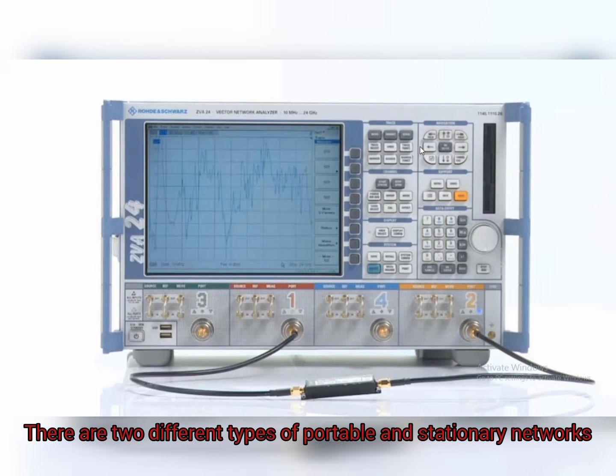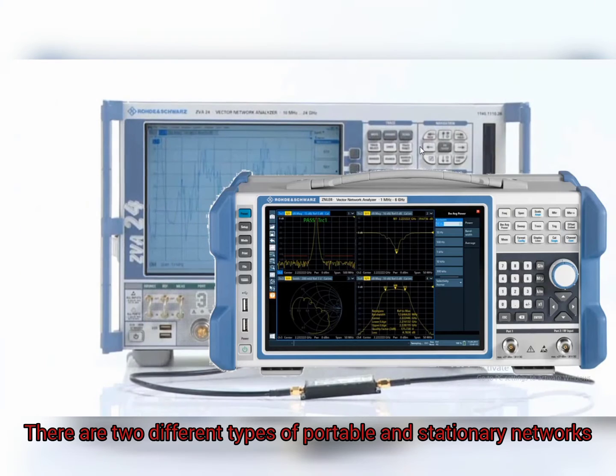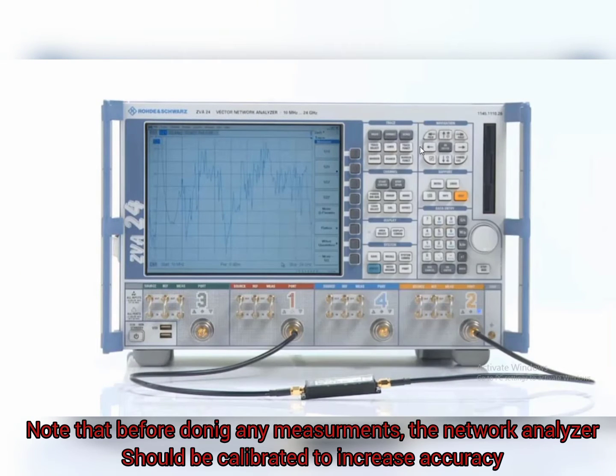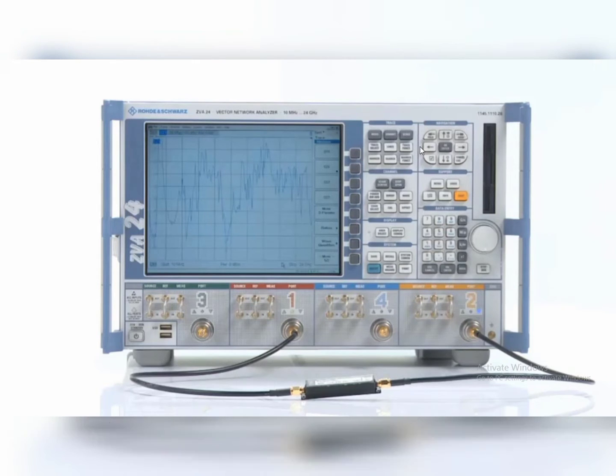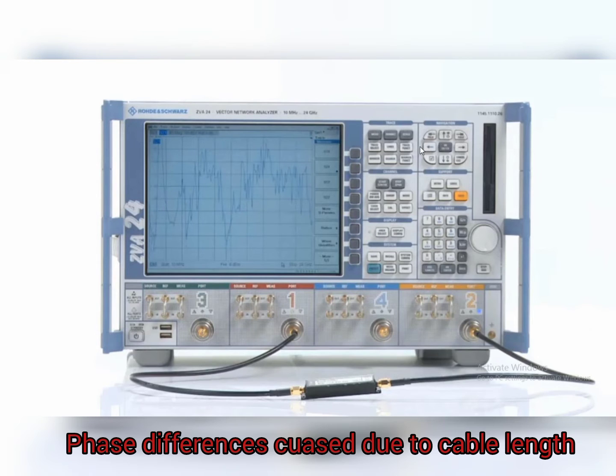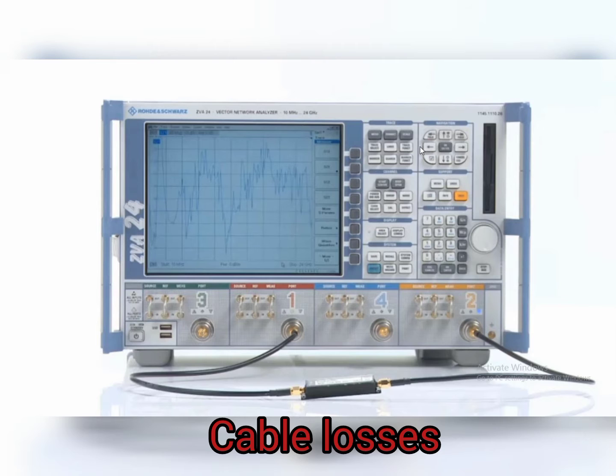There are two different kinds of portable and stationary networks. Note that before doing any measurement by network analyzer, it should be calibrated to increase accuracy. Calibration reduces the errors such as phase differences caused by cable lengths, crosstalk, cable losses, and others.